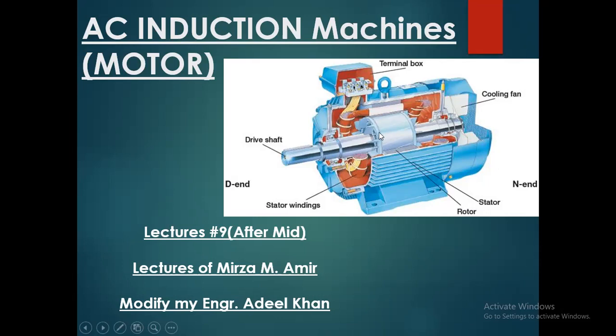The fourth mechanism is to cool down the rotor, because the rotor is continuously rotating in the motor, and these are holes which are available all over the 360 degrees of the AC induction motor, from this side to that side, from start to end. Then these are the stator. The stator is the outermost part in which the rotor rotates. The rotor is inside, in between the stator winding. This one is the shaft which drives any rotating mechanism. This whole winding we call the stator windings, and that's all about the components of the AC induction motor.